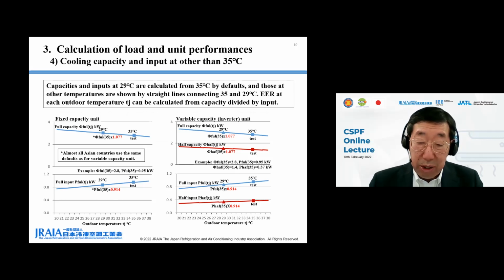This page shows cooling capacity and input at temperatures other than 35 degrees C. The left figures show full capacity and input at each outdoor temperature Tj for fixed capacity unit, and the right figures show full and half capacities and inputs at each Tj for variable capacity unit. Respective capacities and inputs at 29 degrees C are calculated from 35 degrees C values multiplied by the defaults shown in the figure.